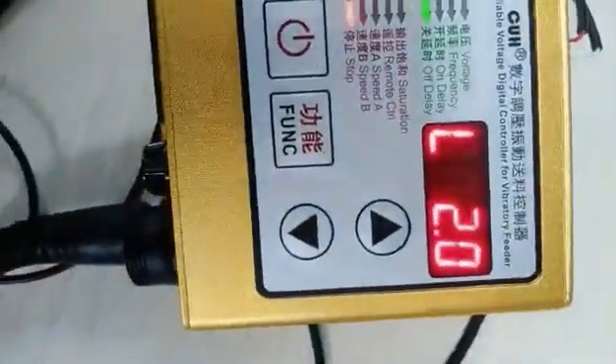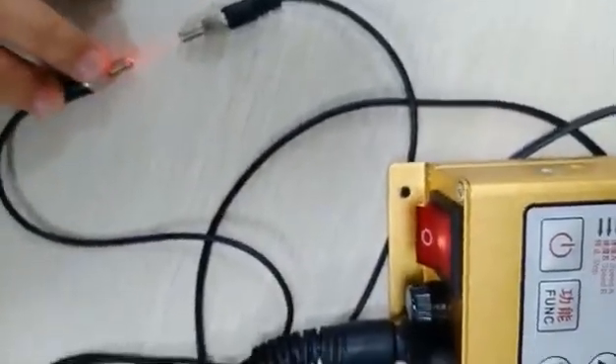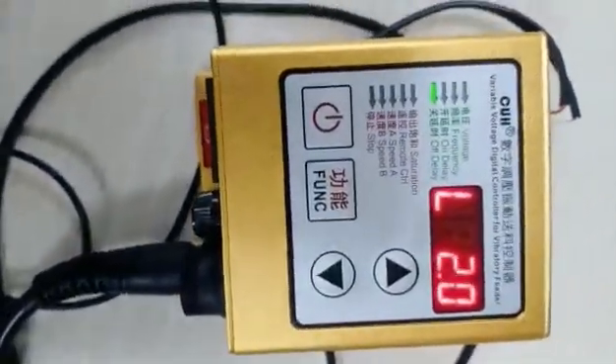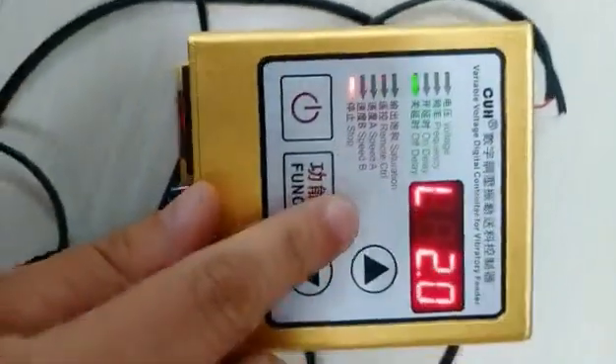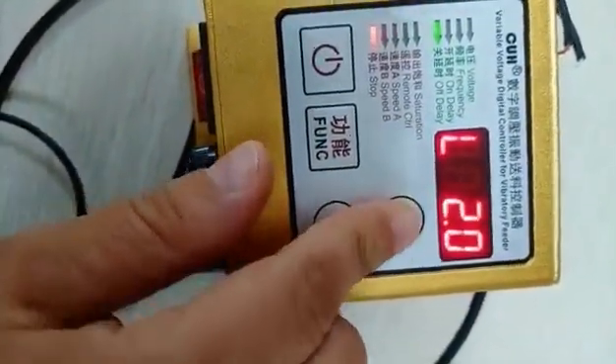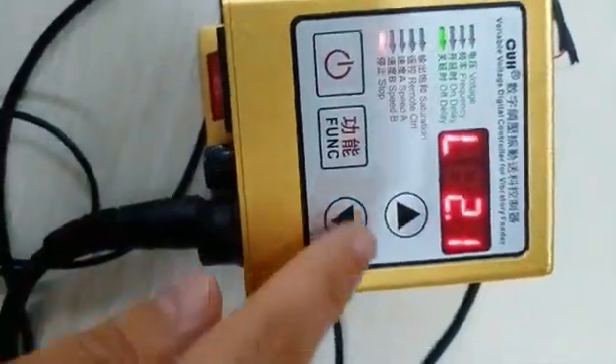So normally when your parts go through, go past the sensor, it does not need as long as two seconds. So we set the off delay time as two seconds. Normally in less than one second your parts can go through the sensor.